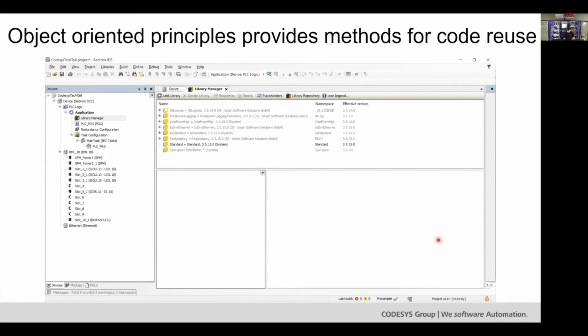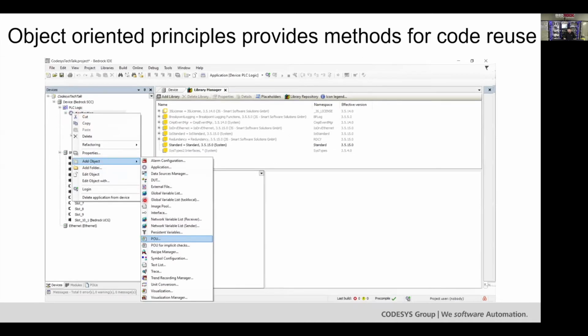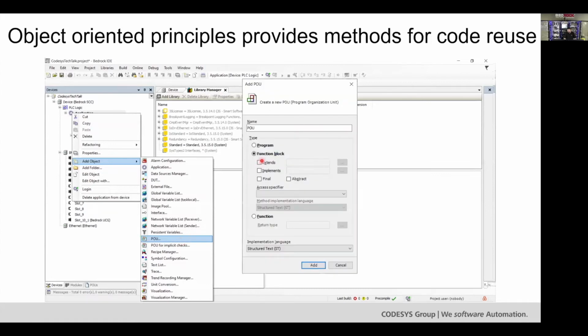What that ends up looking like in the CODESYS environment is you come into a standard project, right-click an application, add an object, add a POU, and you can choose to do a program, which is a common thing to do where you'll just be doing a one-off code write. But more importantly, when it comes to object-oriented programming, is the ability to do function blocks. These function blocks also have the ability to do extends and implementation. We'll talk in a bit more detail about what that means, but this is the core component to building object-oriented programming, and it makes it very simple in the CODESYS environment.